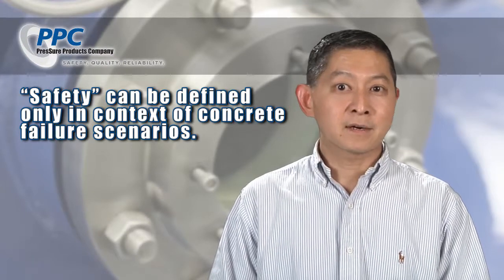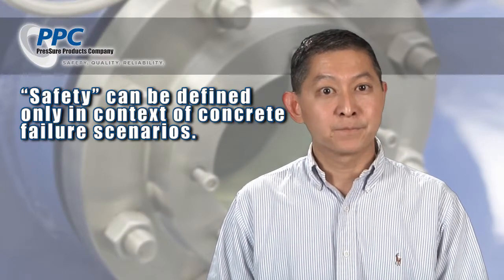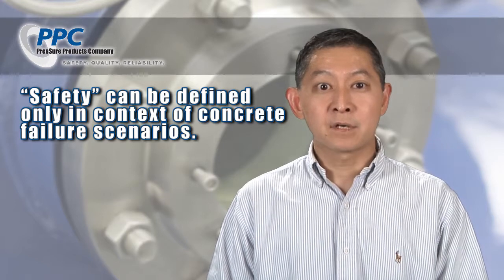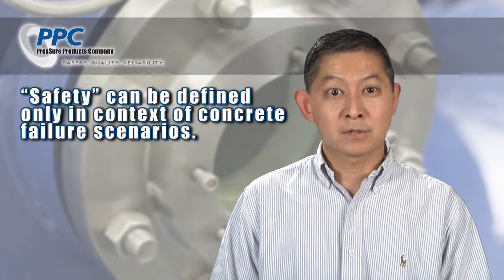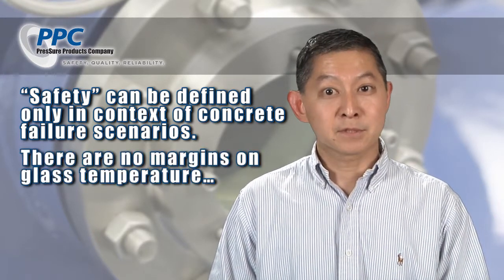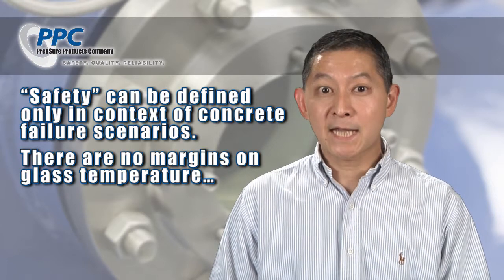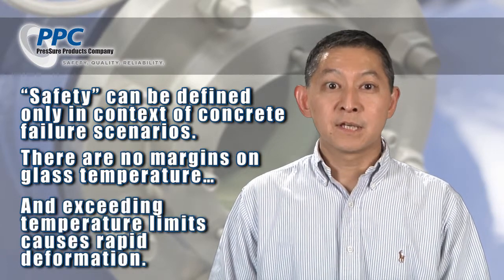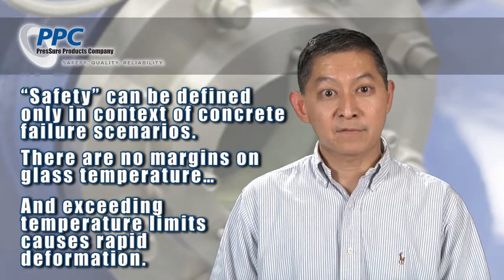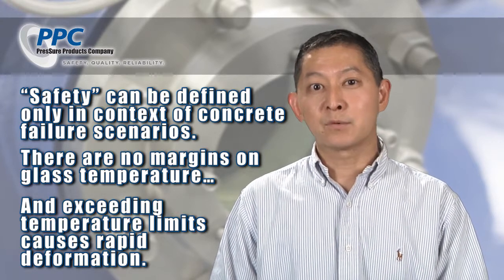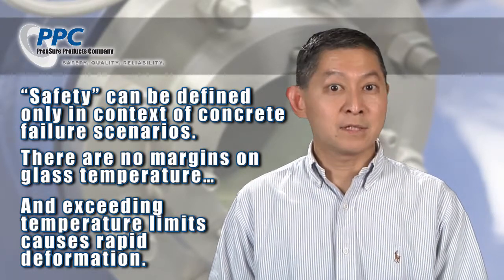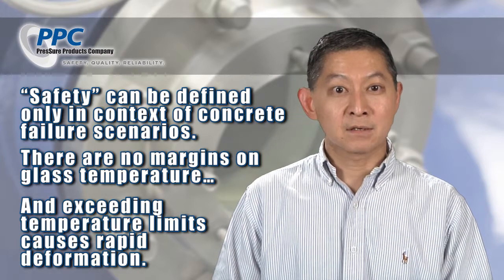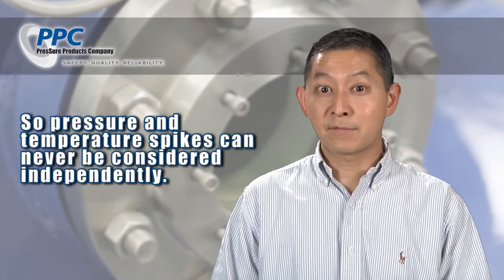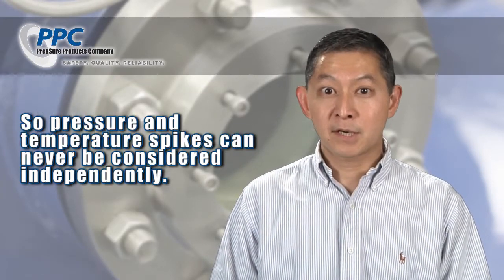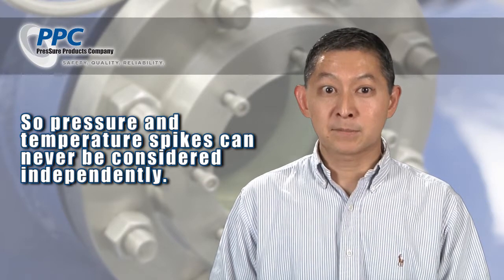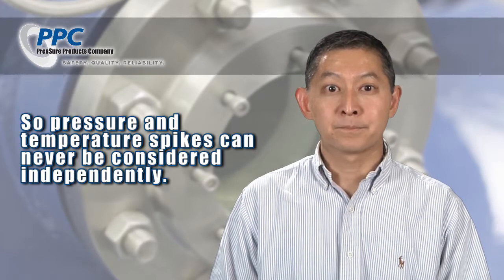You may have heard that glass is a liquid in very slow motion. When glass is heated even a little bit above its maximum surface temperature, this very slow motion becomes considerably faster, and the glass will deform permanently. If you are not aware of this kind of behavior of glass, you might think to yourself, well, if this sight window can take 280 C forever, surely it'll take a little pressure spike. You should never think that way. In a compressor scenario, pressure spikes come with temperature spikes and glass will deform.